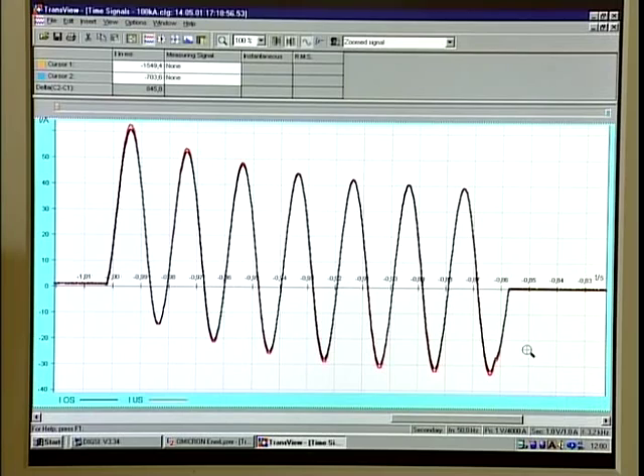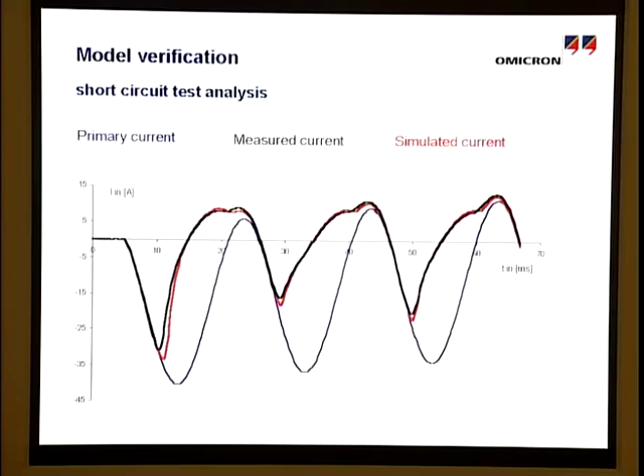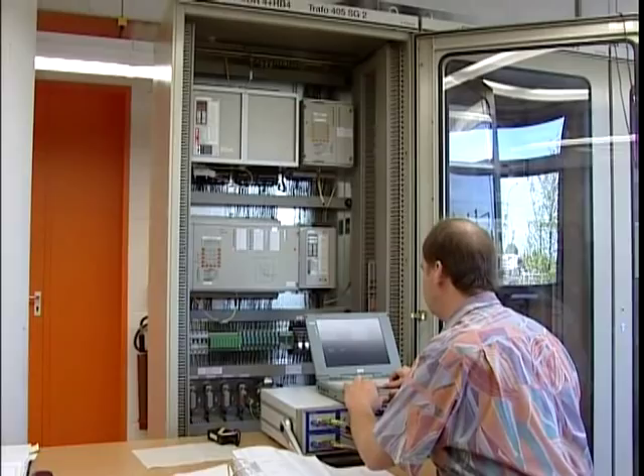If the measured saturated current of the iron core CT and the current calculated theoretically from the hysteresis measurement are analyzed, an excellent correlation can be ascertained. Thus, the suitability of this model can be proven. Should the algorithms of the protection relays not be known sufficiently and therefore offline simulation cannot be performed, the test is effected with the theoretically calculated signals by means of the secondary test set CMC256 and by transient data output.